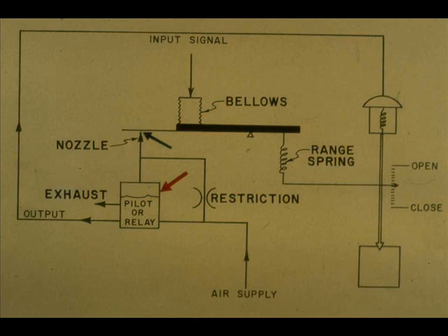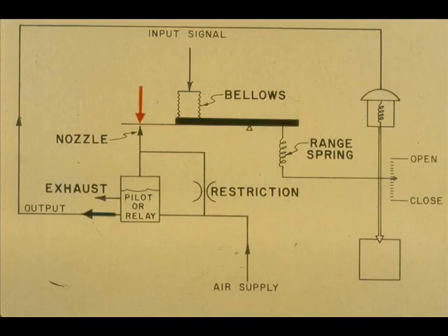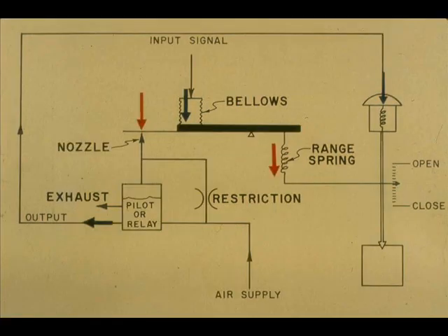By adding a pneumatic relay and a flapper nozzle assembly, we can affect a change in valve stem position for a change in pressure to the input bellows. An increase in pressure in the bellows causes the flapper to cover the nozzle. This immediately causes full output from the pilot. The increased air on the control valve diaphragm moves the stem downward, pulls tension on the spring, and restores the flapper nozzle relationship.